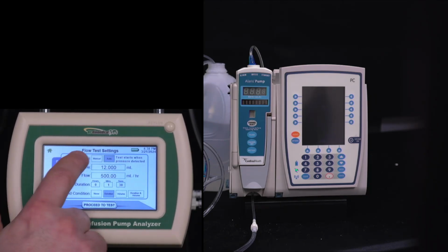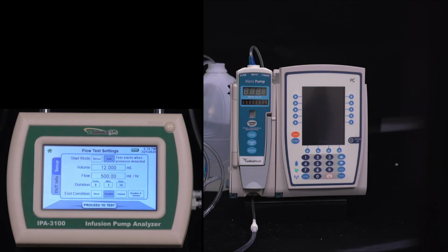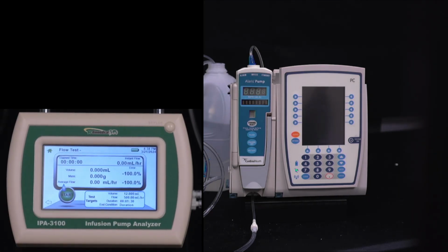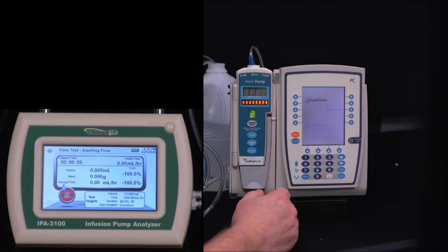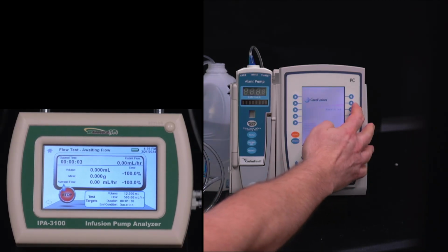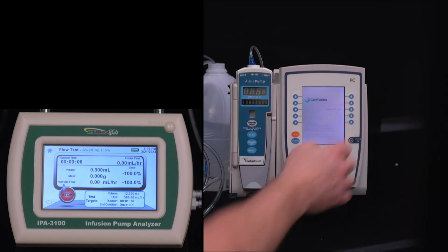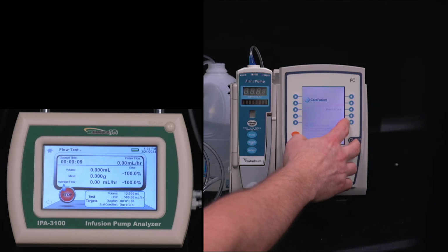And then we have start conditions as well. It can either be a manual start or an auto start. I like the auto start because it's going to sit here and wait. It's going to ask me to prime the system because I just drained it. Now, when I start the test, it's idle, it's ready to go. So I'm going to start this here, and now it's waiting for flow. So I don't have to start the pump. Sometimes you have to press start on the tester and start on the pump at the same time. In this case, we have the freedom to configure the pump and get all of that going without having to worry about timing. So I turned on the pump here, and it's going to do its normal setup stuff.